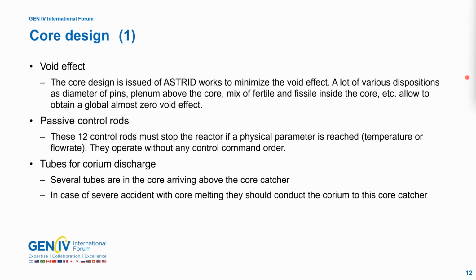Then we have added the core passive control rods. We have two groups of active control rods, but we have a third group of 12 control rods that stop the reactor when a physical parameter is reached. For example, if the temperature of sodium is more than 600 degrees, they fall without any control command or order. It's totally passive control rods. They can stop the reactor if there is a problem.